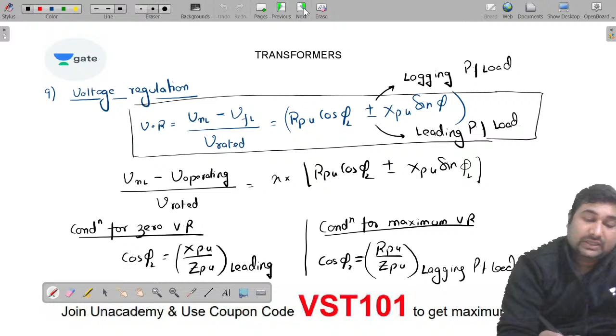A special case is zero voltage regulation. It's easy to recall: zero voltage regulation is X by Z, while normally we remember R by Z for maximum. So you can easily remember the conditions for maximum and zero voltage regulation. This differs for different transformers, depending totally on the R and Z values, i.e. the design parameters of the transformer.